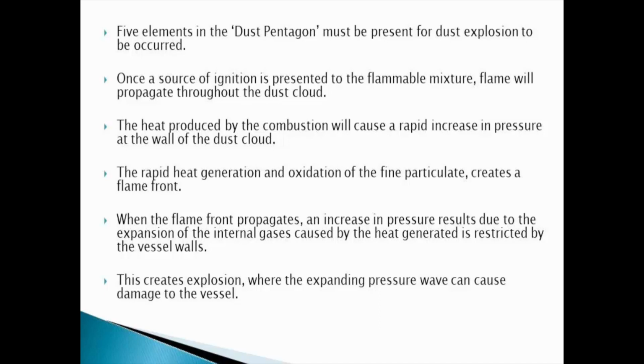The heat produced by the combustion will cause a rapid increase in pressure at the wall of the dust cloud. The rapid heat generation and oxidation of the fine particulate creates a flame front. When the flame front propagates, an increase in pressure results due to the expansion of the internal gases, caused by the heat generated being restricted by the vessel walls. This creates an explosion, where the expanding pressure wave can cause damage to the vessel.